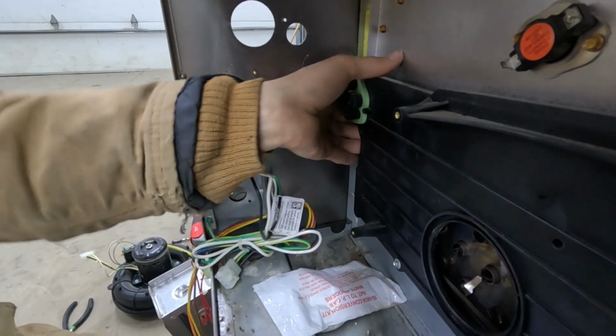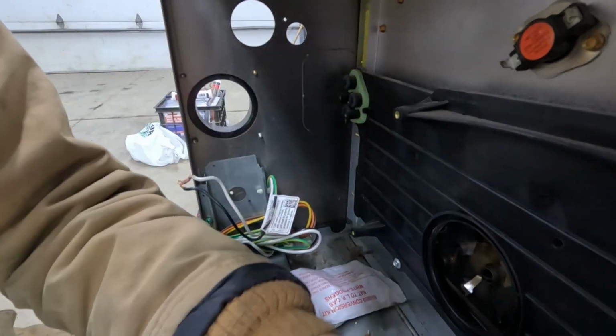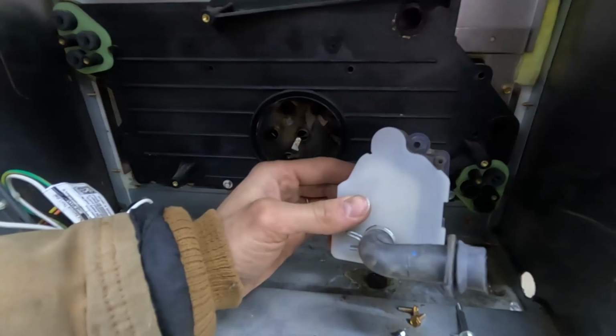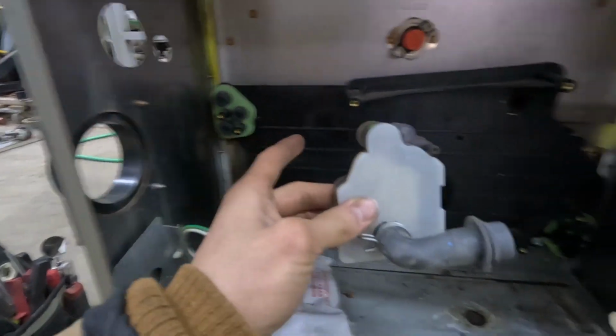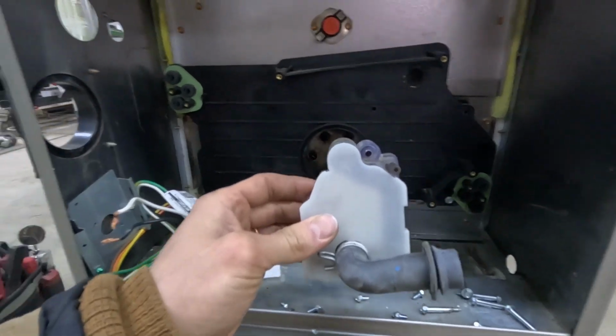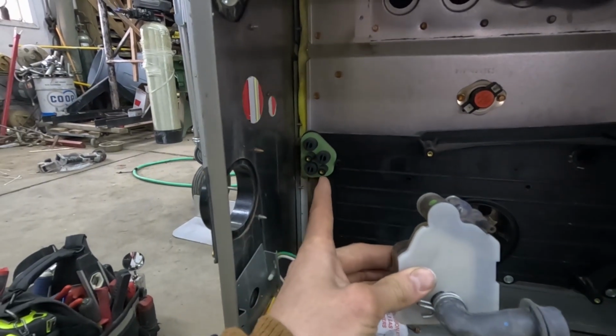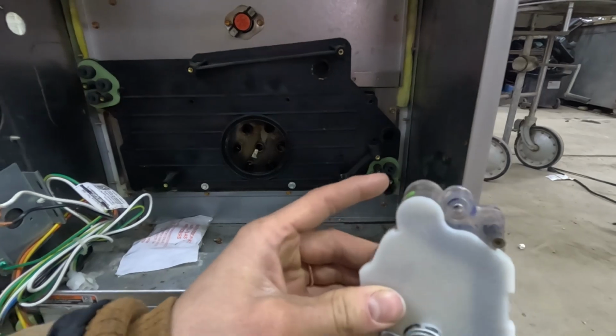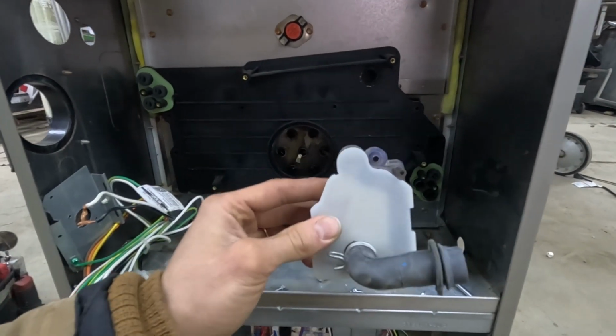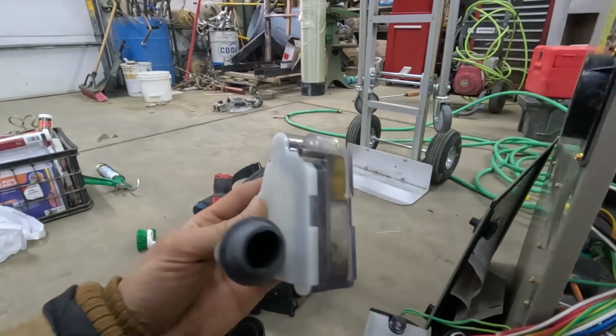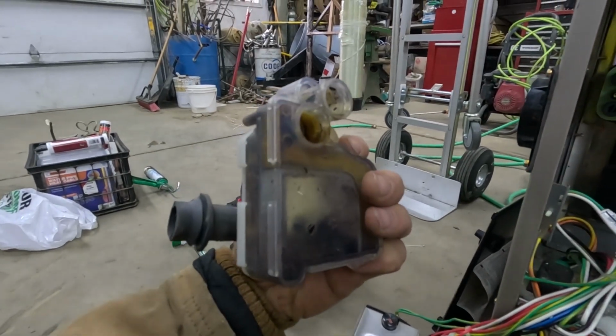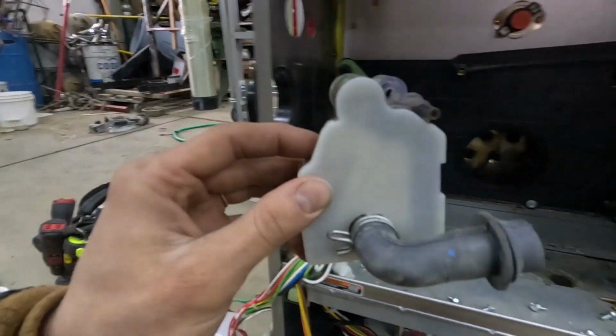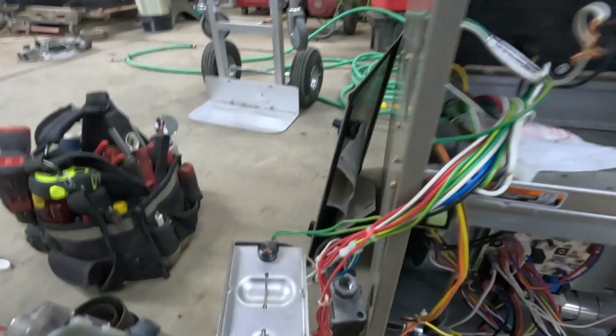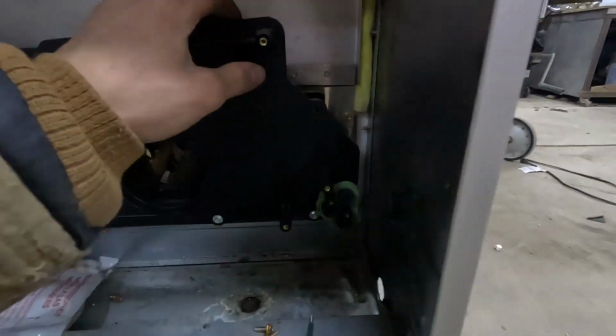I don't like how those aren't pulling out. Large percentage of those are not coming out. Since we do actually have an extra gasket right up there, we're going to go ahead and remove this, and then we'll just move that new gasket that's up there down to here. Because if you do remove this, they do recommend that you replace that gasket. But that's obviously up to your discretion. If you put it back on and it doesn't seem to be leaking or anything, then you're probably okay. It's just what they recommend.